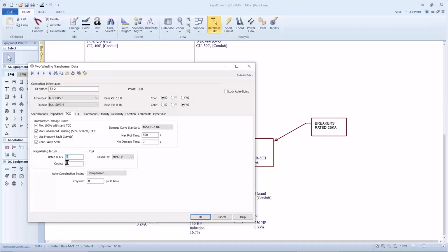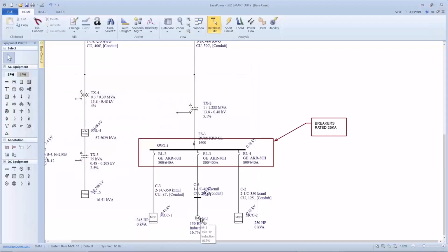And based upon the number of cycles, if I wanted to be conservative, I might increase this to 8 or 10. So again, based upon the manufacturer, these are typical numbers for larger transformers. By all means, use information that you get from the manufacturer. And if you didn't attend last week, I think I went through all this information on transformers in fairly good order.